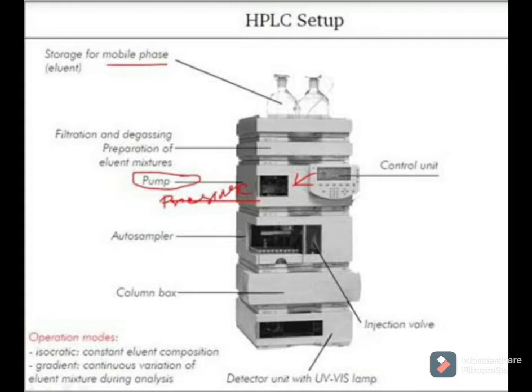I will tell you all the compartments of this Agilent HPLC. First, the top compartment, where you see 4 bottles. These are the mobile phase bottles. When you are using a gradient system, you require 2 or 3 mobile phases also. So there are 4 ports, A, B, C, D, where we keep our mobile phase. After that, coming a little bit down, this is the pump module, the pump compartment. Here we do purging, and any troubleshooting that comes up, we rectify here.